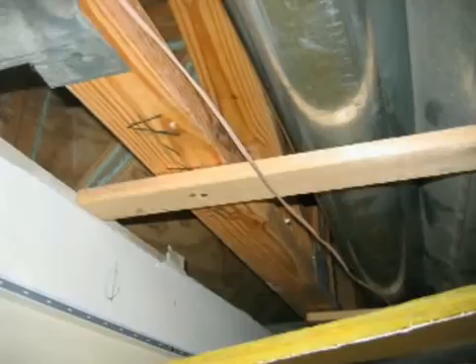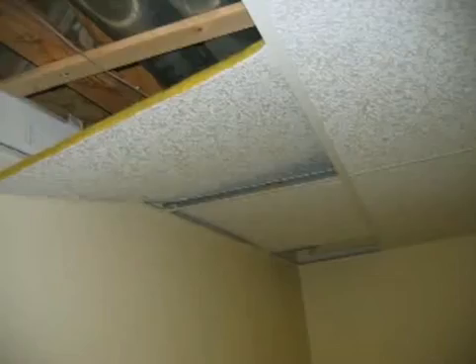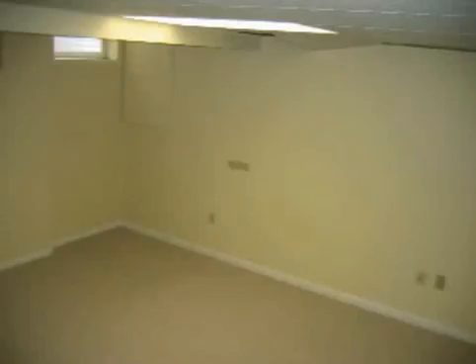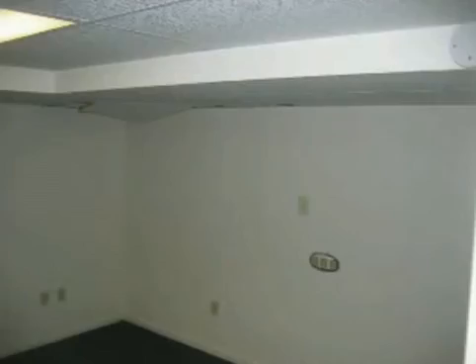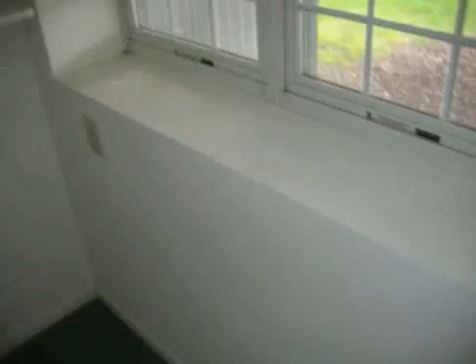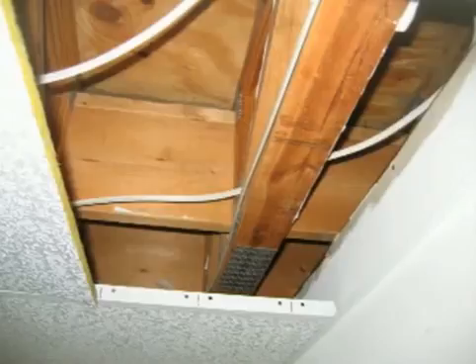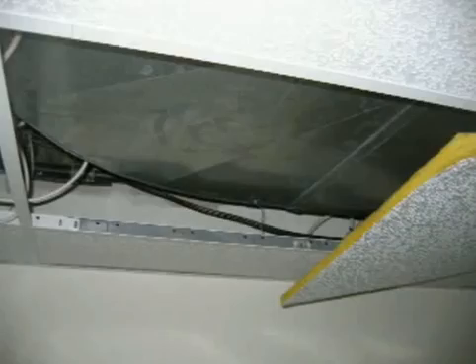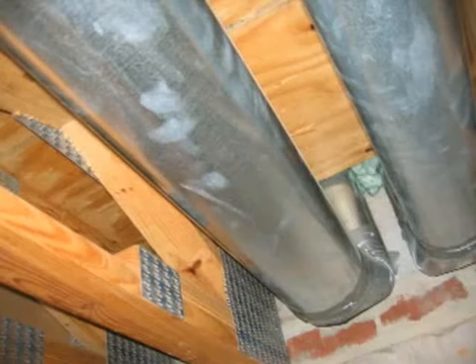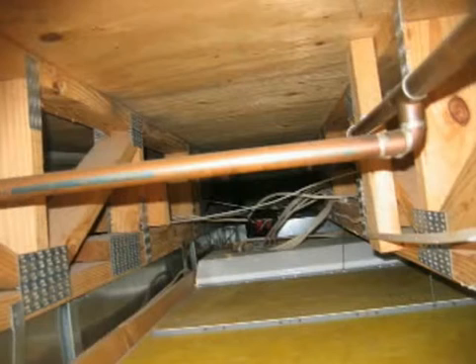So then I started looking all over the place. Opening up the ceiling panels, taking a look above, in corners, nooks and crannies, looking for signs of moisture intrusion, because we have one area that was hidden, really. It's very difficult. I think I just came by it by mistake looking up. Cold ductwork sometimes produces condensation above the ceiling tiles. Looking for water leaks above the ceiling.